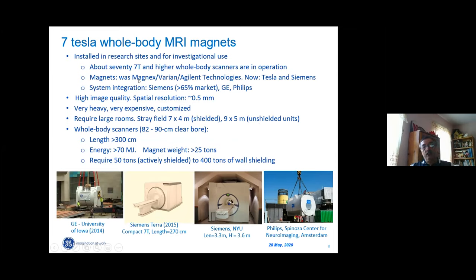They were produced initially. It was Magnex Scientific that started production. Then this company was a part of General Electric, then Varian, Agilent. Now they are produced by Tesla Engineering in England and Siemens. I think Tesla Engineering is in the southern part of England, and Siemens is in Oxfordshire, Siemens Medical Systems. System integration is done by Siemens, General Electric, and Philips. The greatest advantage is excellent image quality. Spatial resolution is on the order of half a millimeter.